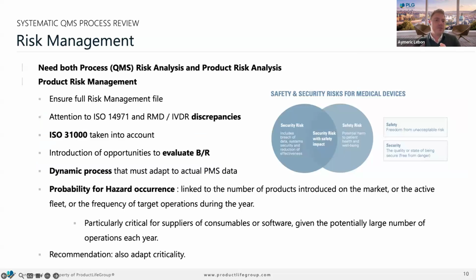I will move to the risk management process. The main thing we see from a pure QMS point of view is that sometimes the risk analysis is really focused on your product, and the process risk analysis is forgotten. Usually it is a finding. In fact, as a global entity, you have a full QMS with different processes, from management review, HR management, infrastructure management, and here you have to have a global risk management. So first, you need to have both risk management files.